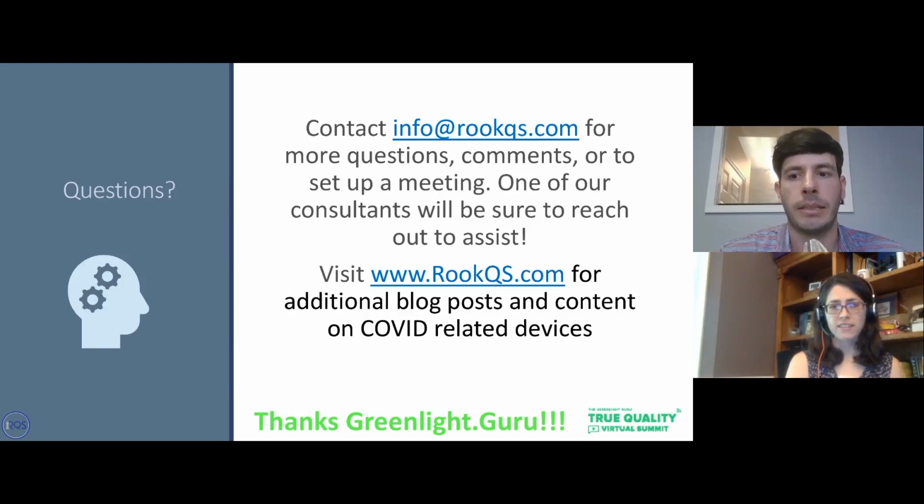So the FDA did say that there was a 60-day extension on all of those. That came out, I think, in March or April, that they are just adding 60 days to your normal 90-day timeline. Like I said, if you think your product that is currently under a 510K review or PMA review has applications for the COVID pandemic or EUA, I would definitely reach out and make the case and see if there's anything you can do to accelerate that process.